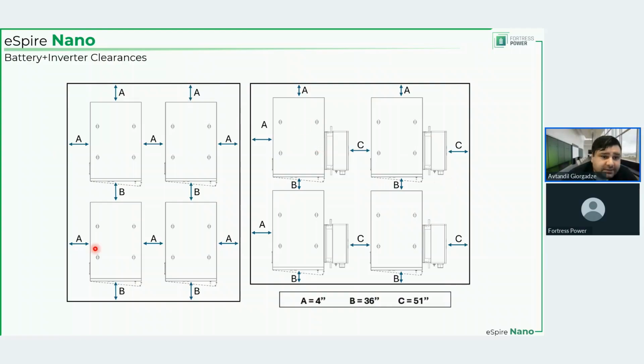So this is it. Obviously, I didn't feel like writing numbers here. So A equals 4 inches, B equals 36 inches, and C equals 51 inches. So you require 51 inches of clearance in front of the inverter. Between the battery cabinets, whether they have inverters attached or are without inverters, the clearance is 36 inches. The clearance between the inverter and the battery cabinet in front of it is 51 inches, so it needs this clearance regardless.